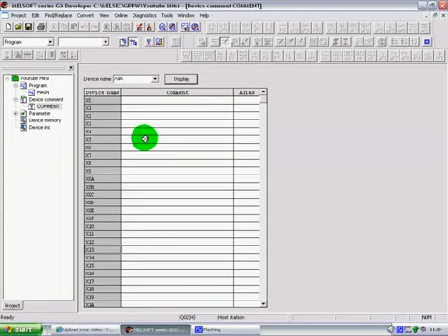If you are familiar with something like Siemens, you notice that they do them in bytes or in words, and they also use the device name starting with I for inputs or Q for outputs, or in German notation it'll be E for inputs, which is Eingang I think, and A for outputs, which is Ausgang. But here in Mitsubishi they do use the hexadecimal.